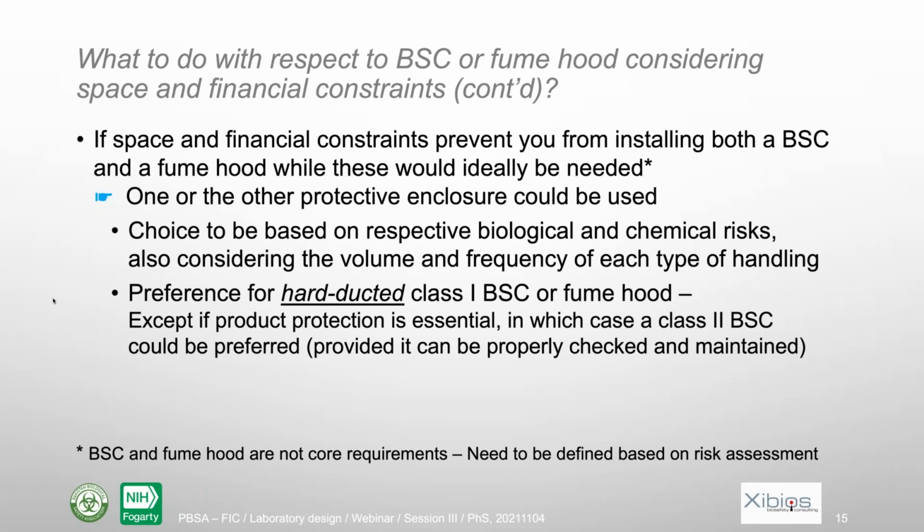There is only one situation where you could prefer a class 2 biosafety cabinet: if the product protection is as essential as the personal protection. In that case, you could have a class 2 biosafety cabinet, but you would have a less good protection versus the biological risk and versus the chemical risk.